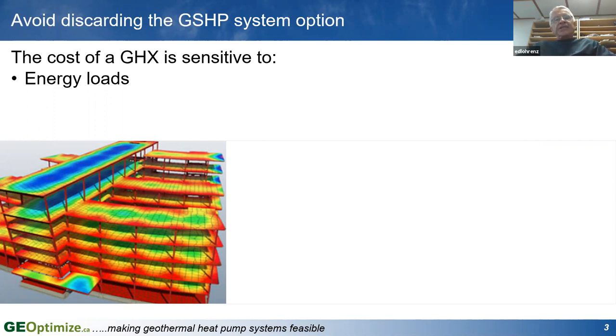if the ground heat exchanger, the amount of pipe that we put in the ground, isn't large enough, the temperature that the heat pumps are going to see coming from the ground heat exchanger is going to get too cold or too warm for the heat pumps to operate efficiently, and they may even quit working.